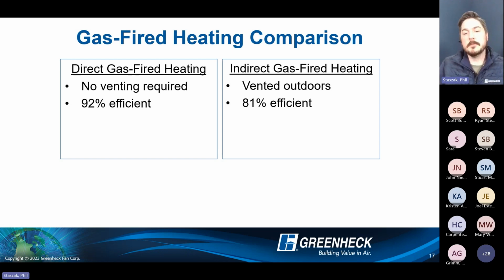That efficiency is limited purposely because we don't want to condense inside that furnace. Condensate's not clean. It ends up eating away at heat exchangers, whether they're stainless or aluminum. And overall, you've got to worry about that water when we're talking about higher efficiency applications. So 81% efficient would be considered a non-condensing furnace. It can be mounted outdoors and you don't have to worry about heat tracing, bringing condensate back in, filtering it, and neutralizing it, which are basically more installation costs.